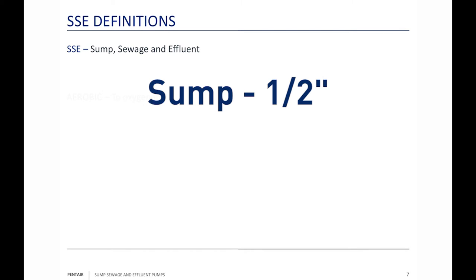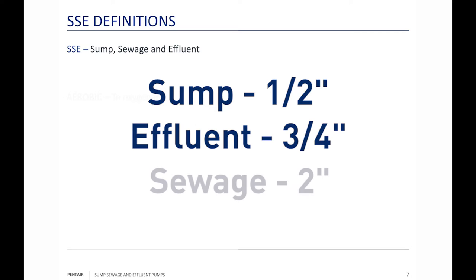The first definition is SSE. It means sump, sewage, and effluent. Some people like to say SES — sump, effluent, sewage — putting them in order of solid size: sump pump is half-inch, effluent pump is three-quarter inch, sewage pump is two inch. The guy that taught me said SSE, so that's the way I do it.